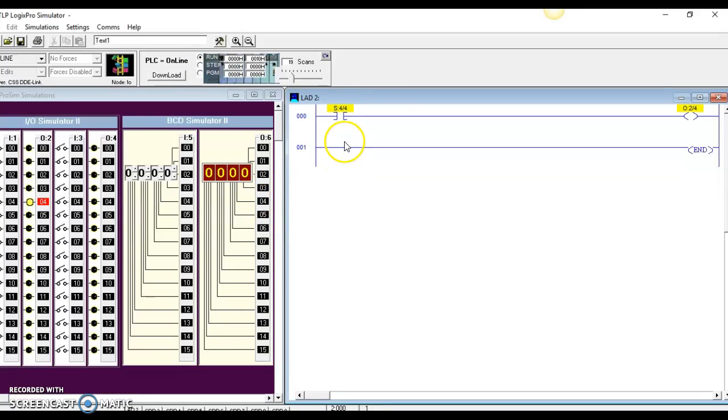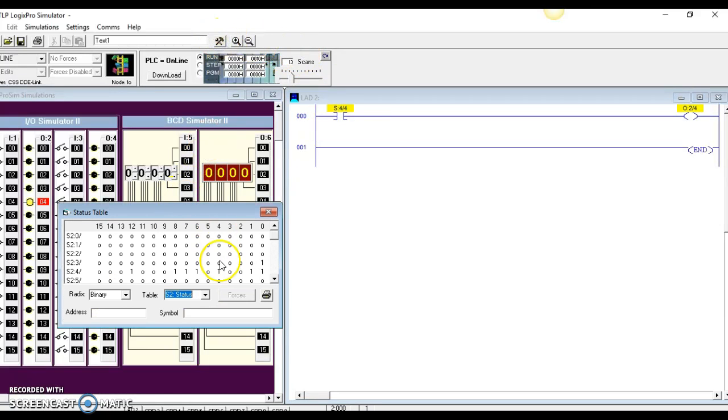So I could set other conditions in here, but just by having this bit in here, which again is right here, this S44 status bit, it's flashing about every other interval. If I use any others, it may be off longer than it's on, or it may be on longer than it's off. But S44 works out to be a perfectly kind of on-off, even interval flash.